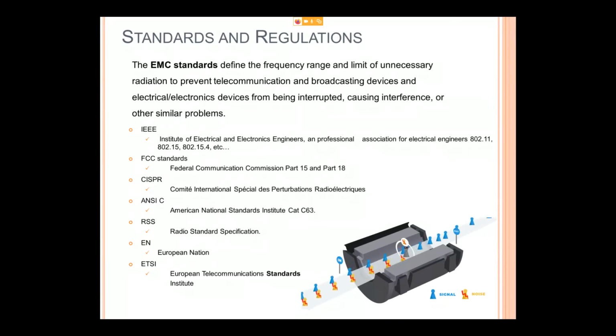There's a limit for any unnecessary radiation coming out of your device. That's called the EMC standard, electromagnetic compatibility standards. We have many standards in the world, and each country has its own frequency range and limitations. So if you're going to ship your device to a country, it should pass their standards and regulations, then get certified with that country's standard, labeled, and then you can sell it inside the country or export it. That's what I've mentioned in this slide.